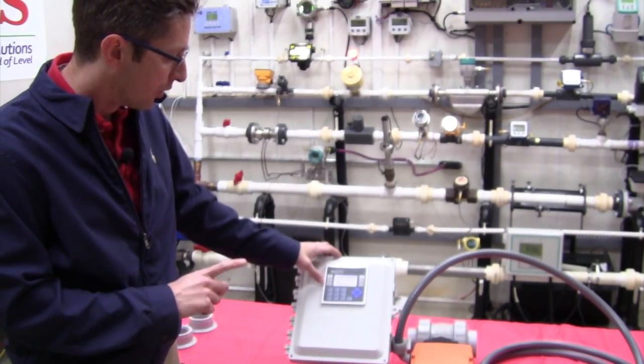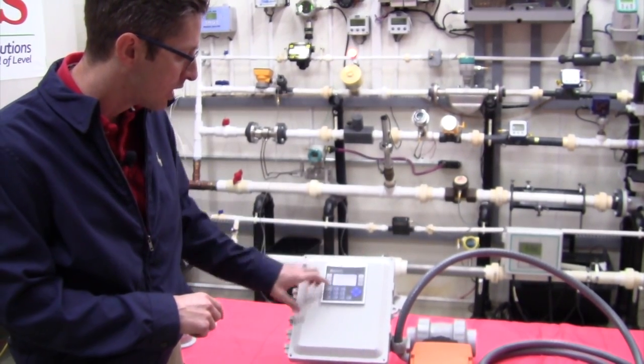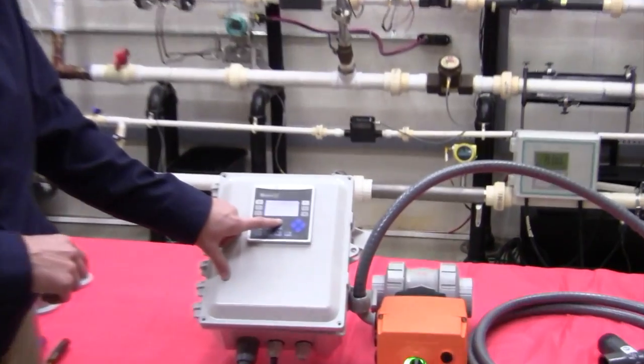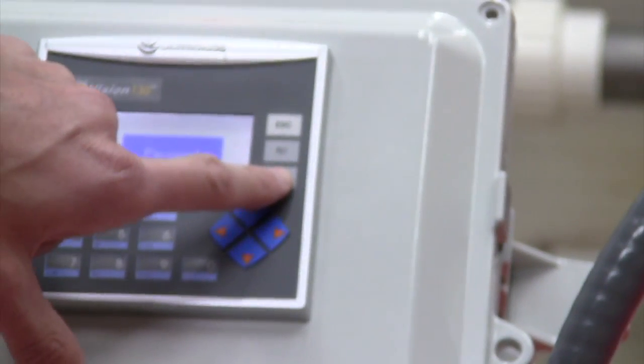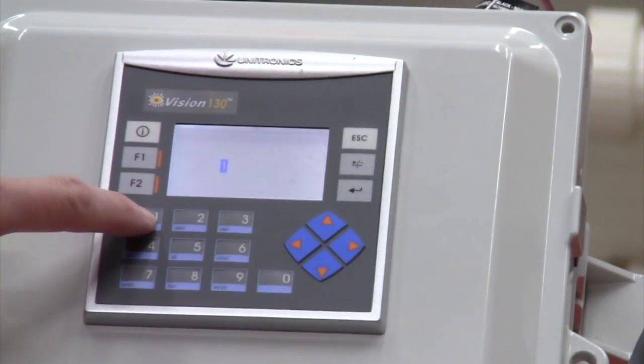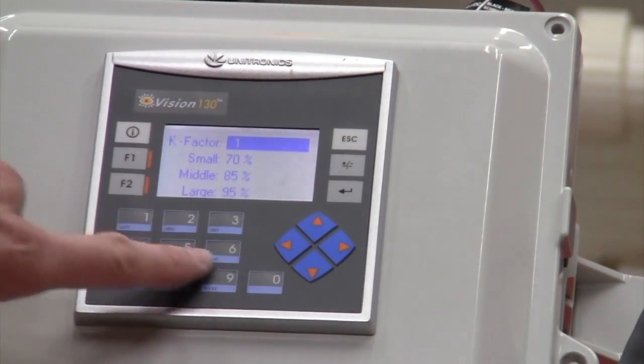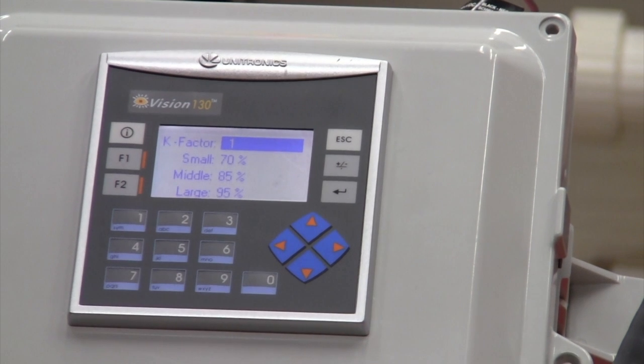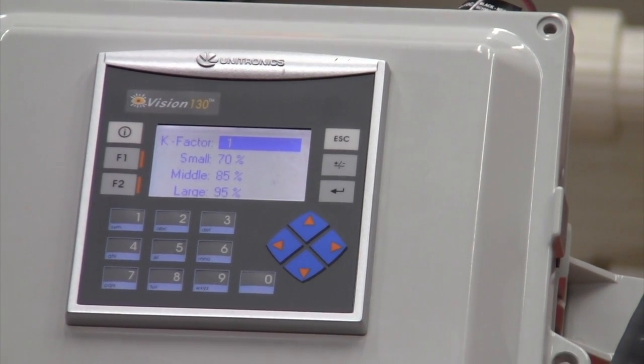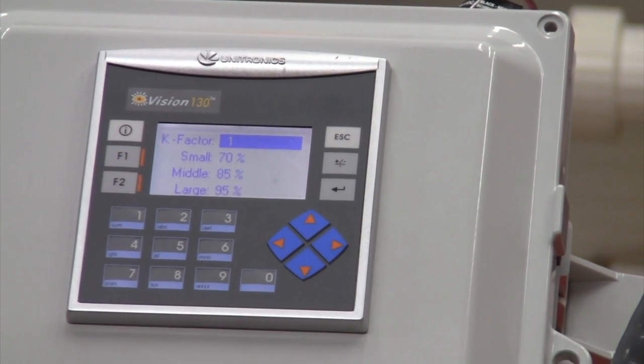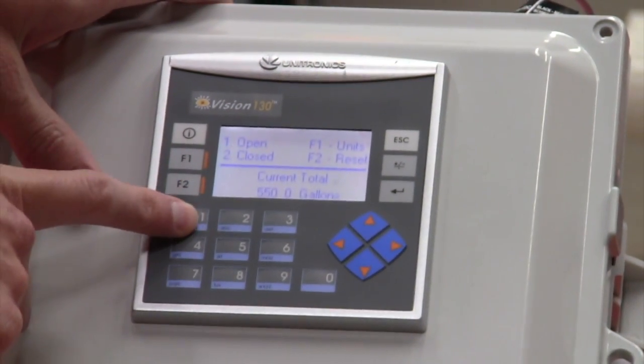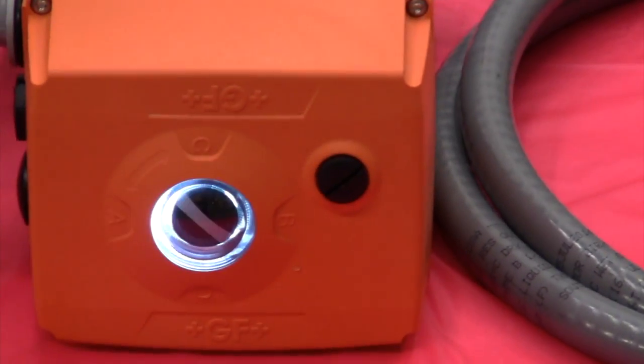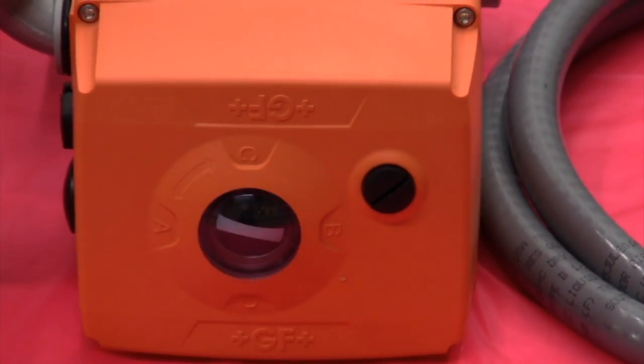Now, the last thing we need to do before we do a calibration is press number 3, go into setup, hit enter, password is 111, hit enter again, and I need my K factor to be set to 1. So what I'm going to be doing here is counting pulses every time that paddle wheel spins. The first thing I'm going to do is escape out of here, go into manual mode, and open my valve.